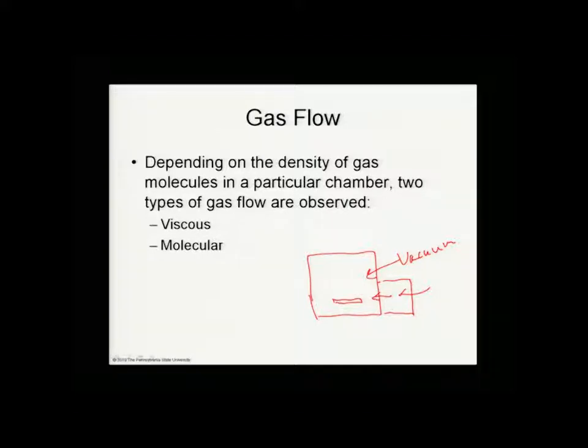So there has to be some way of putting the sample in, pumping it down, creating a vacuum, and then passing it into the pristine processing chamber, and then taking it back out when the process is over. But lots of times in our discussions, we don't bother showing the antechamber or the load lock chamber because we know it should be there in a really well-controlled processing situation.